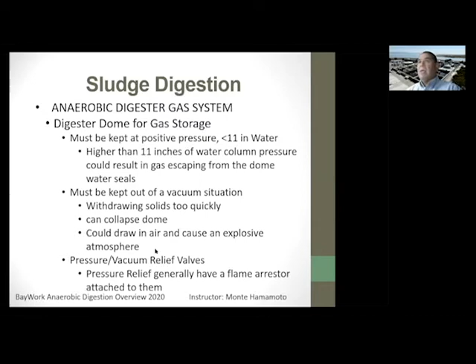There are safety devices, or pressure vacuum relief valves. The pressure relief generally has a flame arrestor attached, so if anything does catch fire, it can't make its way back into the digester. You can see digester gas, get some oxygen in there, and this is what can happen — I believe this happened in the Midwest.